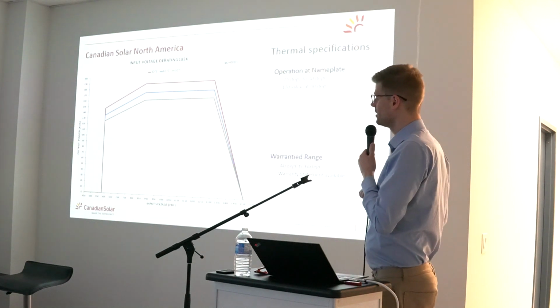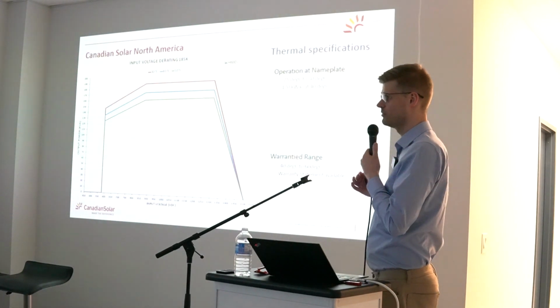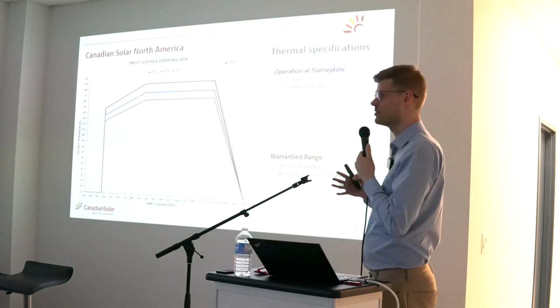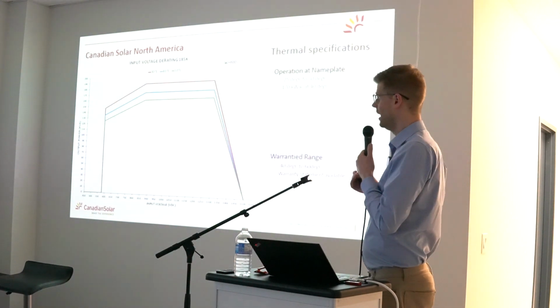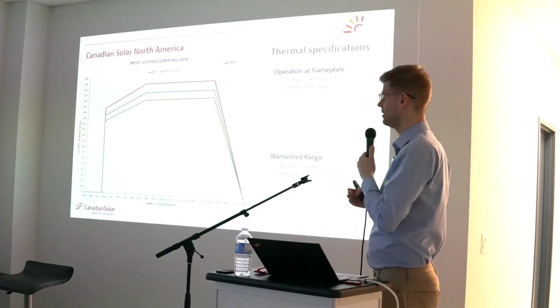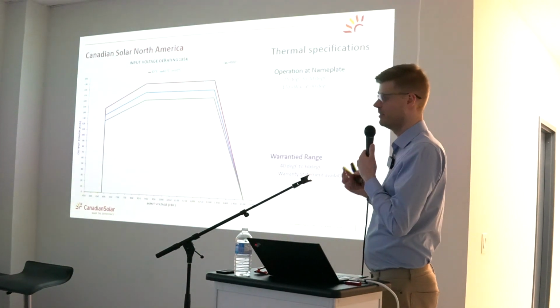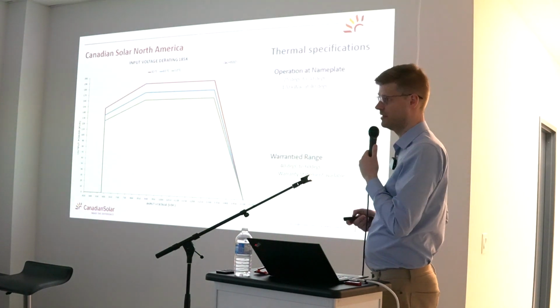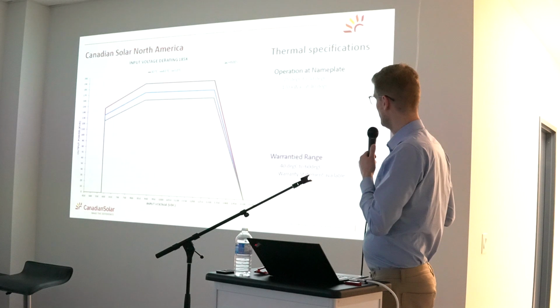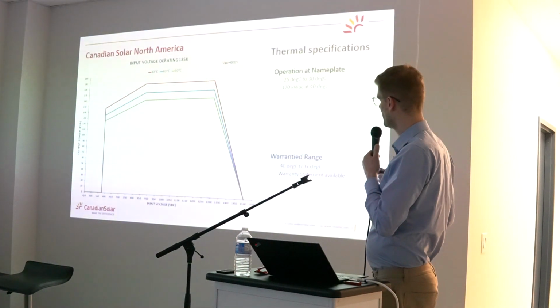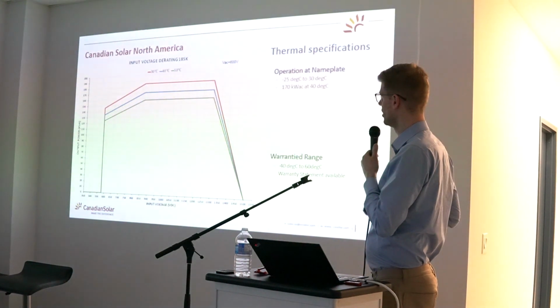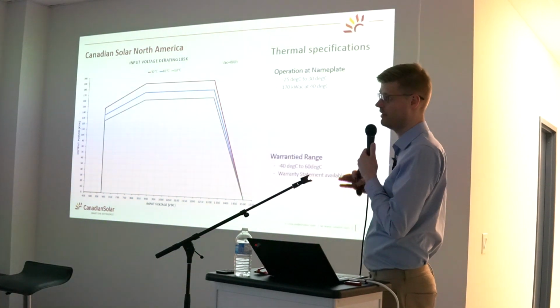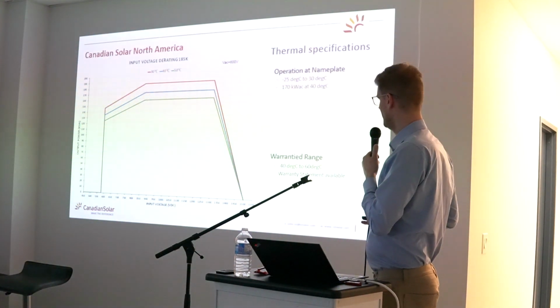For a Canadian market, 30 or 40 degrees on rooftop systems is not very common. It can certainly happen once in a while on a very, very hot summer day, but it's not a problem with these systems to still operate at full nameplate output power for that. And at 40 degrees ambient, it can still produce 170 kilowatts, so we are very close to that 185 the system allows.